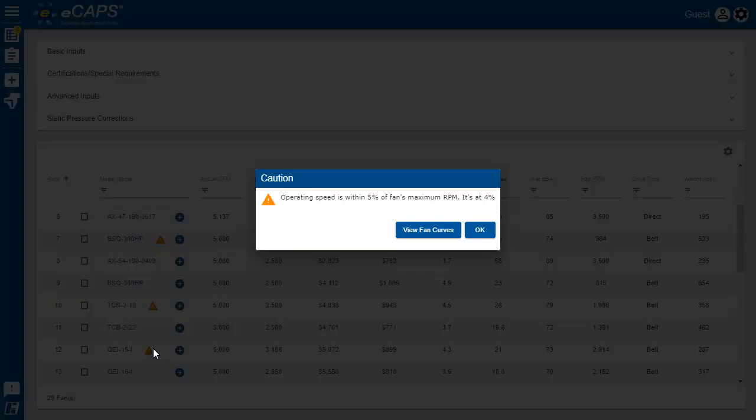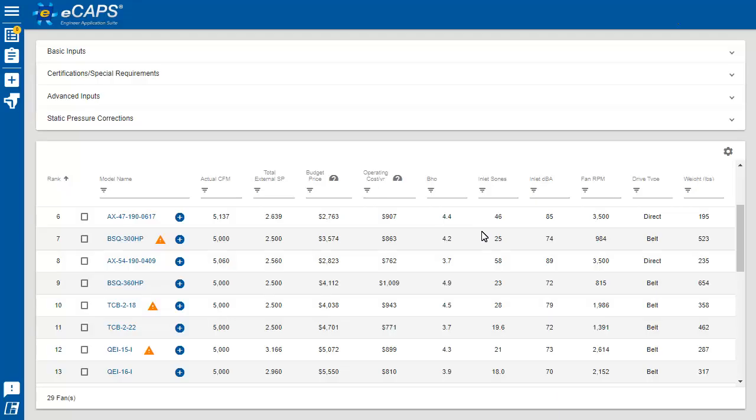Second, when you are within 5% of the maximum speed. We will also caution you when your selection is under CFM and significantly over CFM. And finally, when your brake horsepower is within 10% of the max motor size.